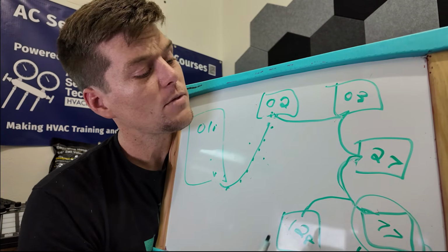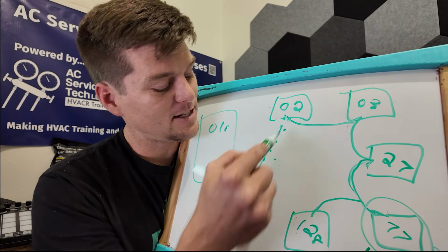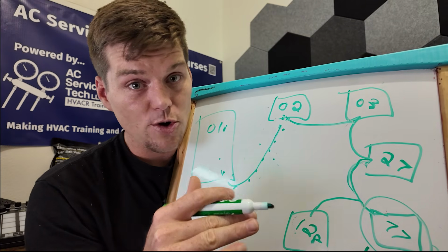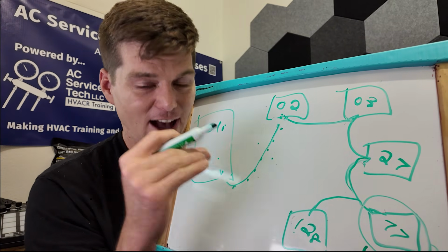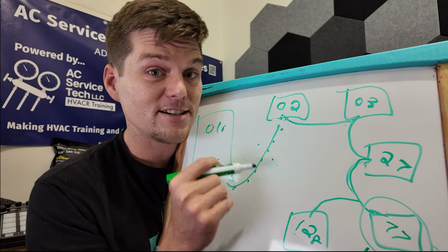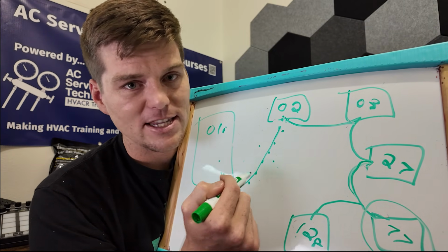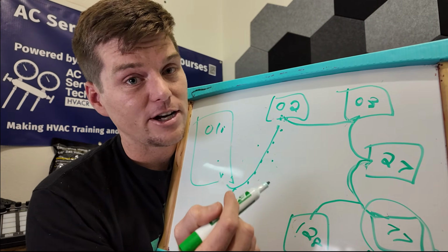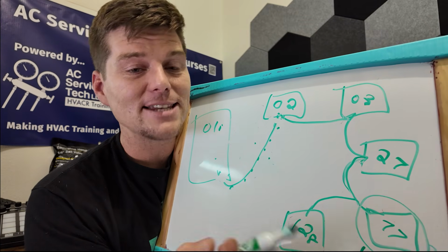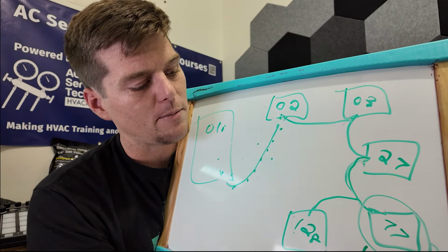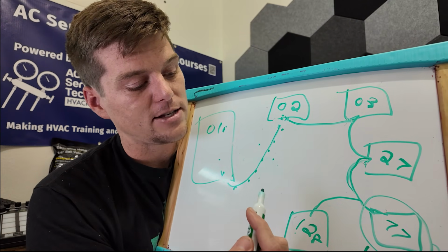So understanding that, if I'm disconnecting wires on both sides and ohming them out looking for no continuity, no connection, and I have continuity, or I have resistance, which is what I'd rather you check, resistance on the wire itself, it's not supposed to be there. You'll find that in certain scenarios, random U4 error codes are caused by capacitance that builds up because of the wires touching each other, because of shielded wire in between. These are all things that we can check as technicians.